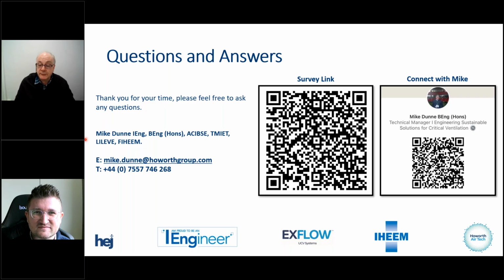I've had one that says, is 80% backup of air supply if an AHU fails a requirement for HTM compliance or a nice to have? No, that's a requirement. So it is referenced within HTM Part A. One thing that I've not actually discussed today is the volumes that we look for. So one of the frequent failures is the volumes of terminals. So at validation, all designs must be at design plus 10%. That's a requirement. If it's at 120%, we fail it. We don't go to site, we say rebalance the system.